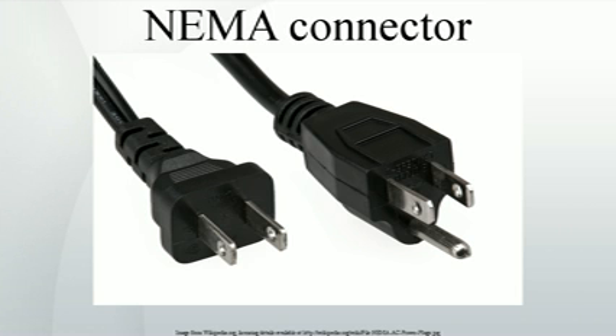Compared to the 5-15P plug, the 5-20P plug has the neutral blade rotated 90° and shifted so its inner edge is approximately 1/2 in (12.7 mm) from the hot blade. The 5-20R receptacle may have a T-shaped neutral hole, to accept both 5-15P and 5-20P plugs. The 5-30 and 5-50 are larger, with 1 inch between power pins. 5-30 also has a bent neutral blade. All of these are uncommon, as twist-locking plugs are generally used for high-current applications.